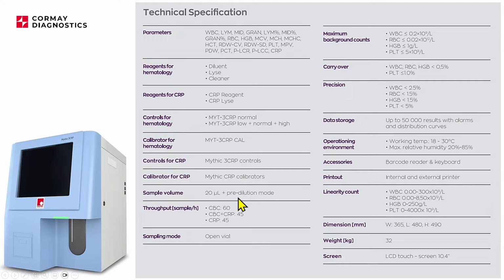Sampling volume is 20 microliters, and those 20 microliters are used for normal aspiration, and in the pre-dilution mode we are also using the same volume of sample. And by the way, this is whole blood. So even the CRP analysis is done on whole blood, and that is the reason for the CRP lyse. Because we are using whole blood, first we need to lyse the red blood cells and dilute everything which is not needed, and then the CRP reagent is used to combine the antibodies which are on the latex with the CRP in the blood. Throughput: CBC, 60 samples per hour, so CBC plus 3D. This is the meaning of that.